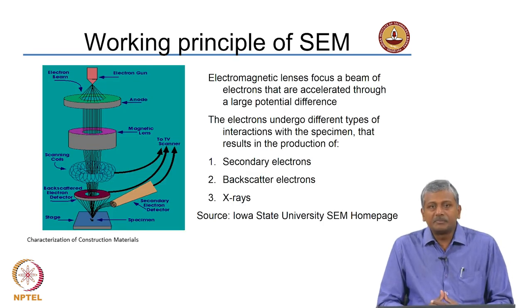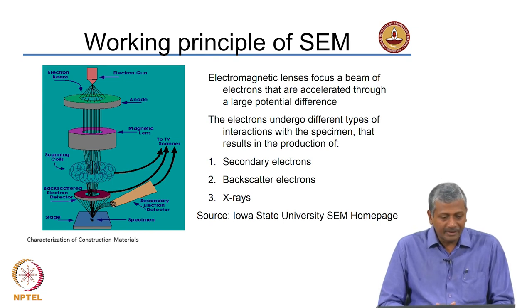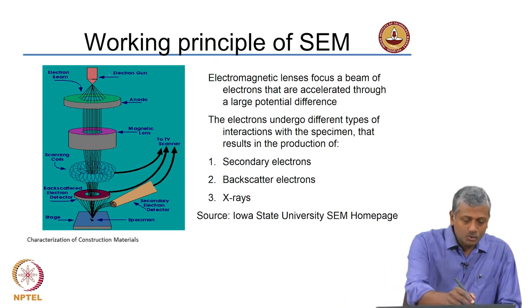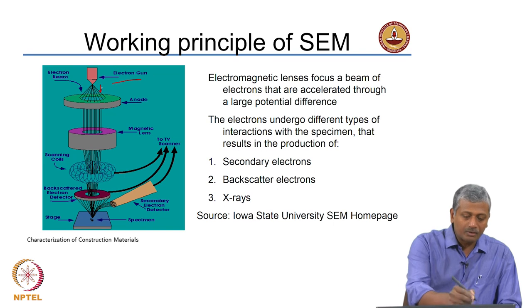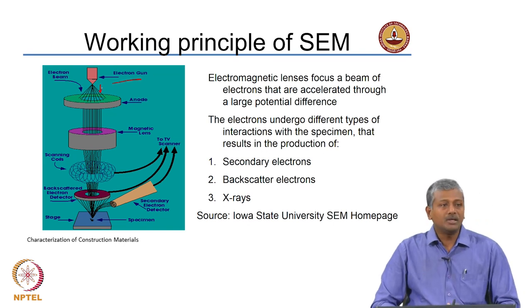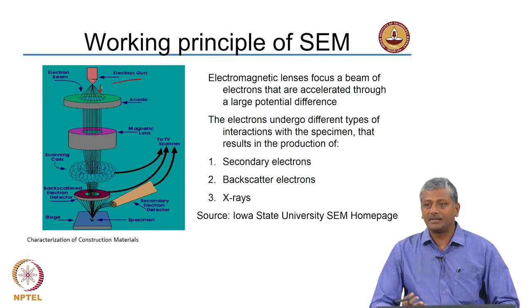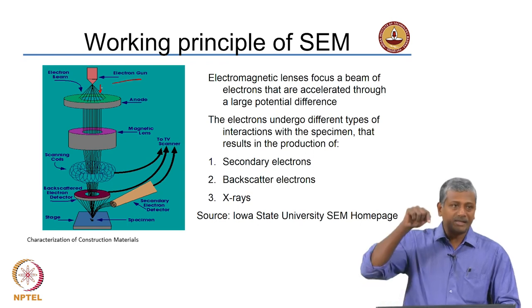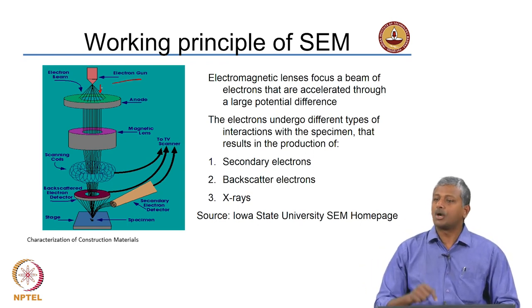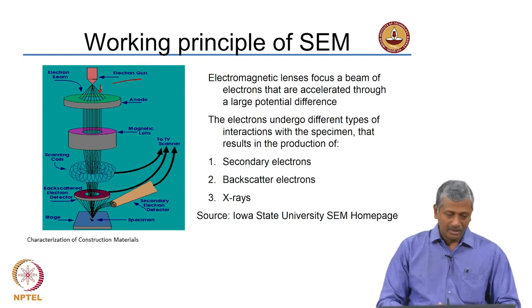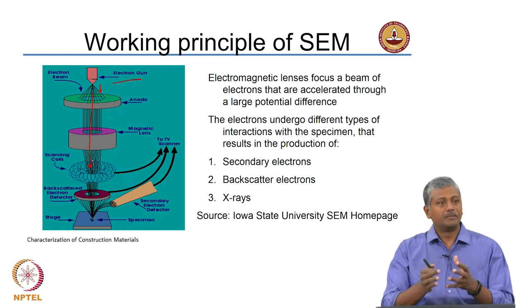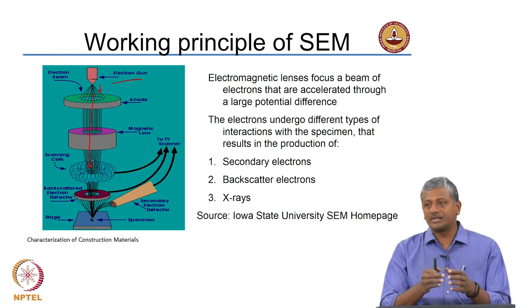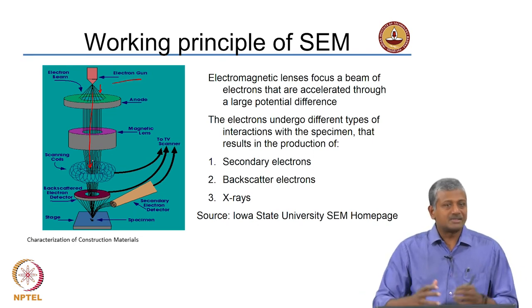The SEM is best understood through its schematic diagram. There is an electron gun from which fast-moving electrons travel rapidly down the central axis of the SEM column — analogous to the optic axis in optical microscopes. All electrons are made to move in a straight line within a parallel beam. This is made possible by the use of magnetic lenses, which by controlling the level of the magnetic field applied, cause the electrons to spiral down the optic axis.